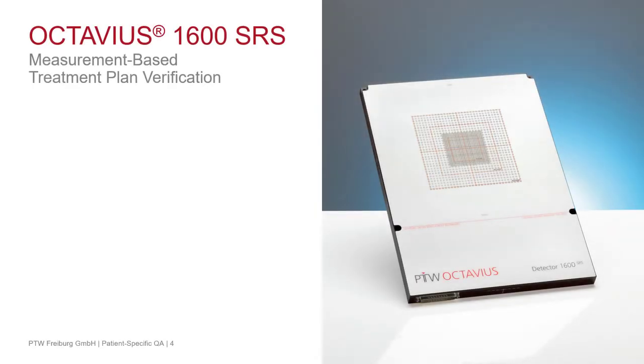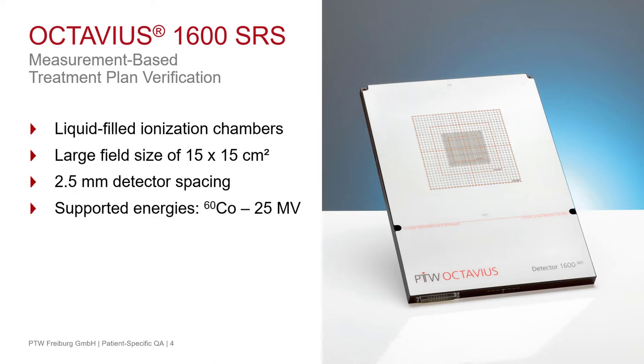One of our solutions for measurement-based treatment plan verification is the Octavius Detector 1600 SRS. This is only one example for the variety of ionization chamber detectors from PTW. It is a liquid-filled ionization chamber detector with a large field size of 15 × 15 cm². The detector spacing in the center area is 2.5 mm and you have a wide range of supported energies, from cobalt-60 up to 25 MV.